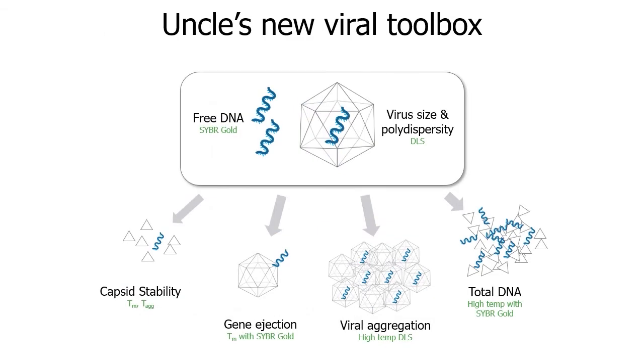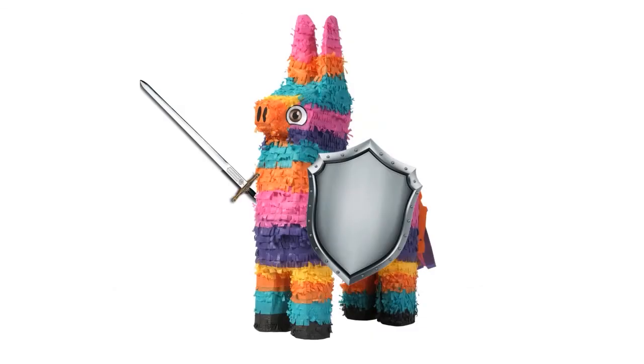Using UNCLE's two lasers and full-spectrum fluorescence, you can look at both pathways of AAV stability — genome ejection and capsid disruption. DLS provides sample quality assessment before thermal ramp and aggregation quantification afterward. The SYBR Gold fluorescence metric tracks free DNA prior to thermal ramp and total DNA released after. Most of this information is available in just one experiment using only one nine-microliter volume of sample. With all this UNCLE data, you can create an AAV that's ready for battle and won't aggregate or fall apart under stress.